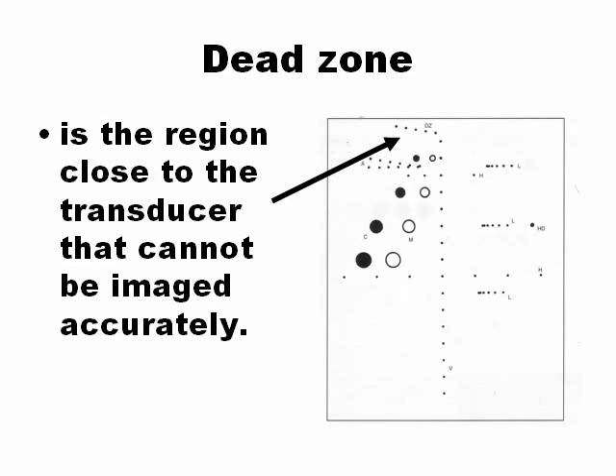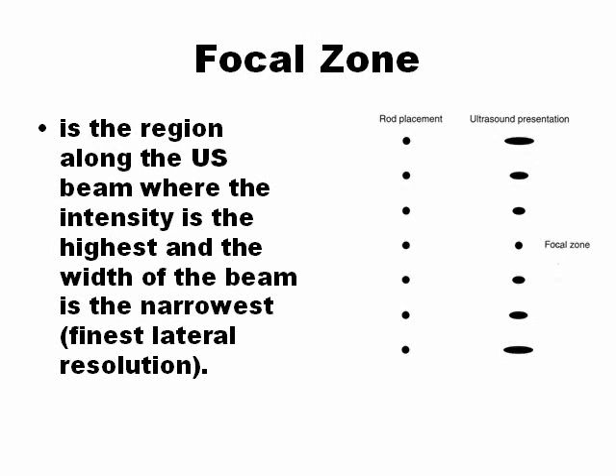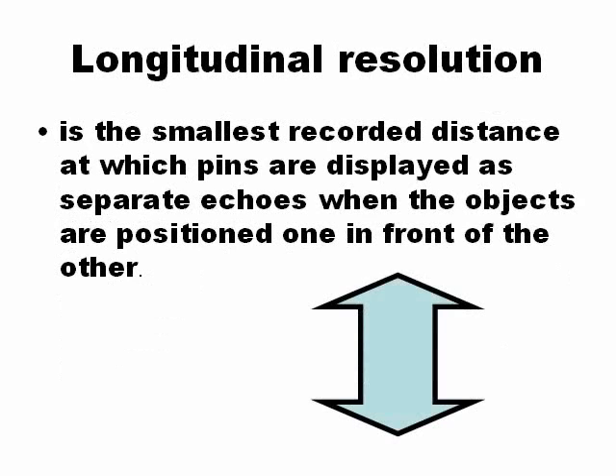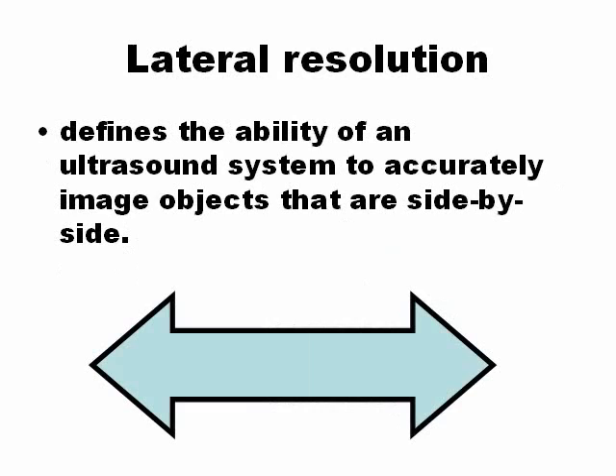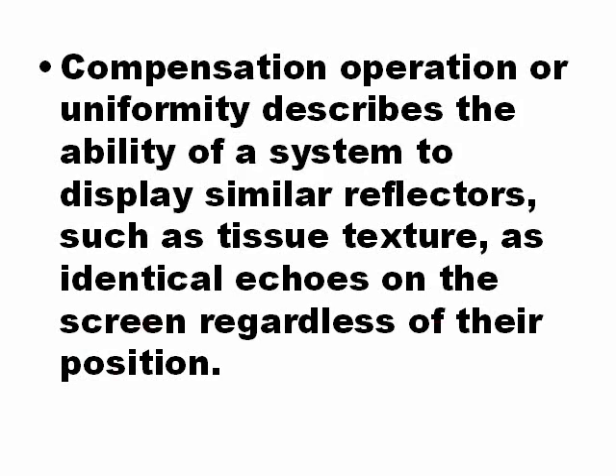The dead zone is the minimum distance at which the machine can see a structure. Focal zone is to determine if the focal areas are in the area that the machine says they are. Longitudinal resolution is the smallest recorded distance between two pins in vertical. Lateral resolution is the minimum distance between two pins when you are in horizontal. Compensation is the uniformity, and that lets you know if the time gain compensation is working correctly. It's about attenuation.